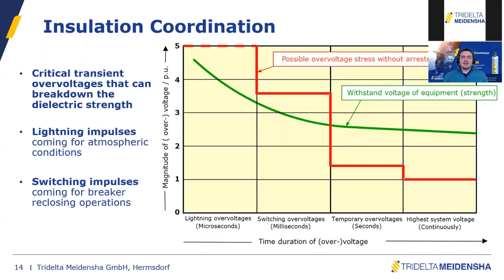Arrester selection is deeply related to insulation coordination. In green, you see the withstand voltage of the equipment, for example the power transformer, the withstand voltage of your windings. On the x-axis, you see switching overvoltages in this area and lightning overvoltages in this area. Lightning impulses and switching impulses are the critical transient voltages that can break down the electrical strength of your equipment. We don't want to exceed this withstand voltage of the equipment.